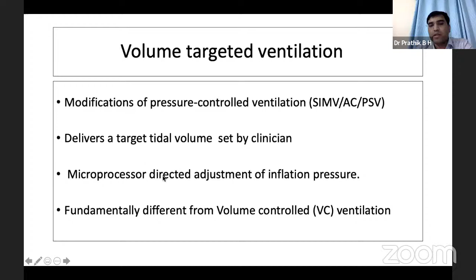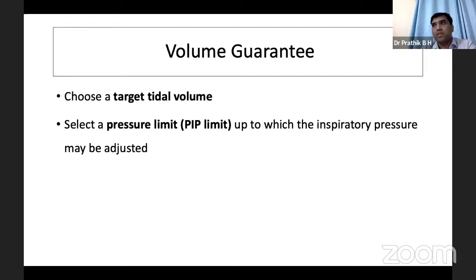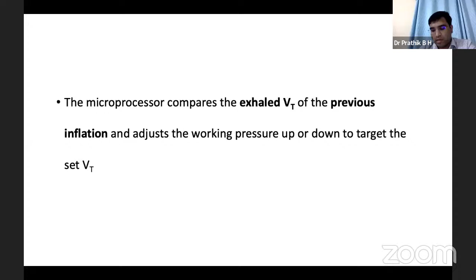Here, initially, the first step is to choose the target tidal volume. Once you choose the target tidal volume, you have to choose the pressure limit or the PIP limit to which the inspiratory pressure can increase or decrease to deliver that tidal volume. So the first step is to choose the tidal volume based on the patient's disease condition and also the gestational age. The next step is to choose the pressure limit. Here you're not going to choose the peak inspiratory pressure, but you're going to choose a limit within which the ventilator will try to give the targeted tidal volume. Then the microprocessor compares the tidal volume of the previous breath and adjusts the pressure. Either it will increase or decrease to deliver the same targeted tidal volume.